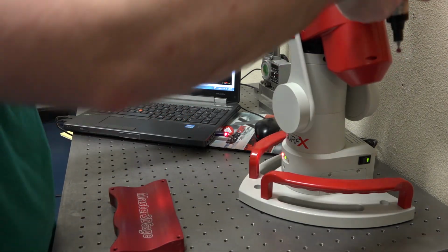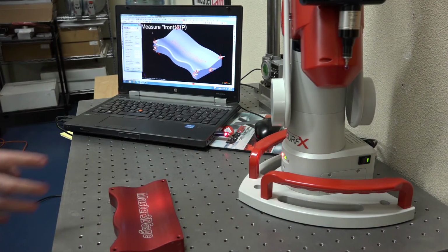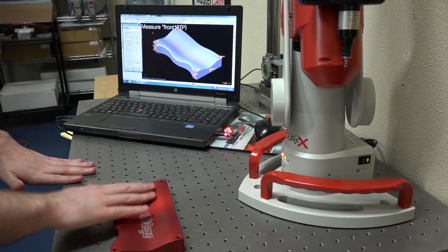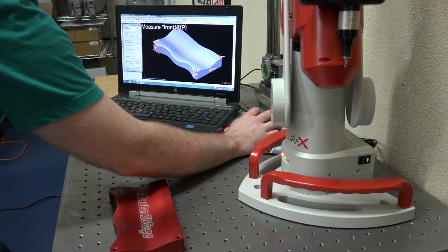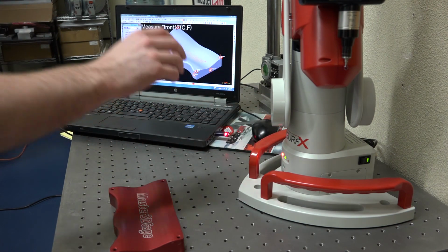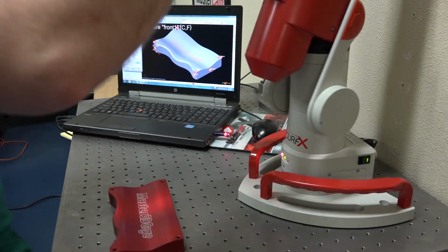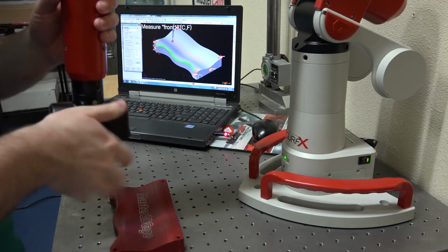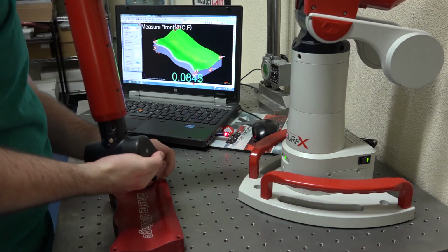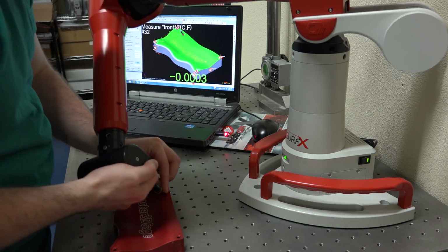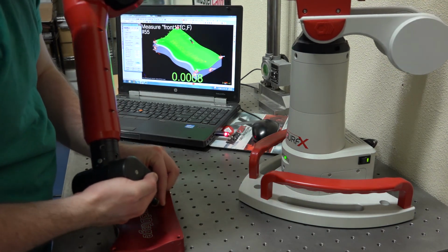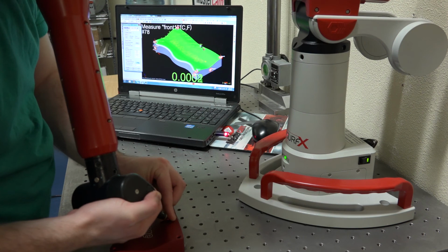Alright, now that I am in inspection build mode, I can actually do a combination of continuous points and inspection mode to lay down points along the surface to compare this complex model. So I'll switch to continuous points mode. Then I can just hold down the button on the 3D Gage arm and it will do a broad spectrum compare and very rapidly gather point data for me.